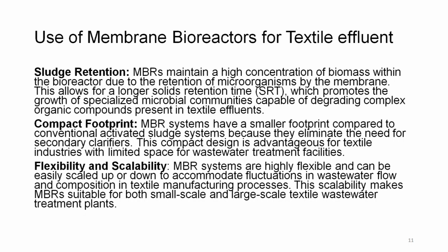Compact footprint. MBRs have a smaller footprint compared to the conventional activated sludge system because they eliminate the need for secondary clarifiers. This compact design is advantageous for the textile industry with limited space for wastewater treatment facilities.